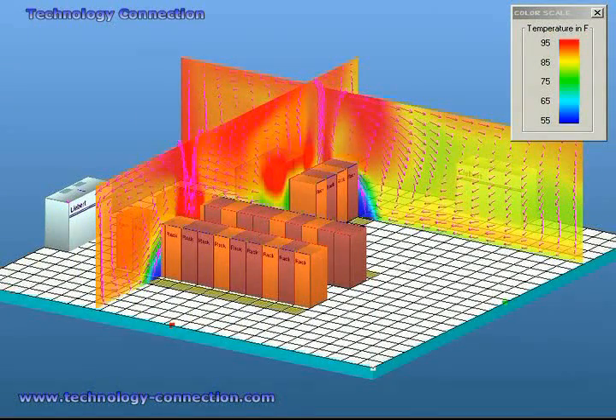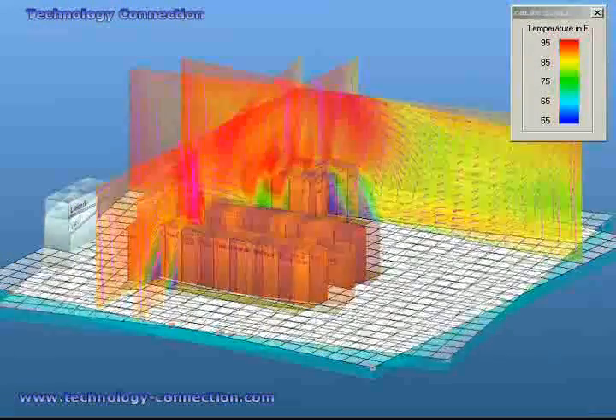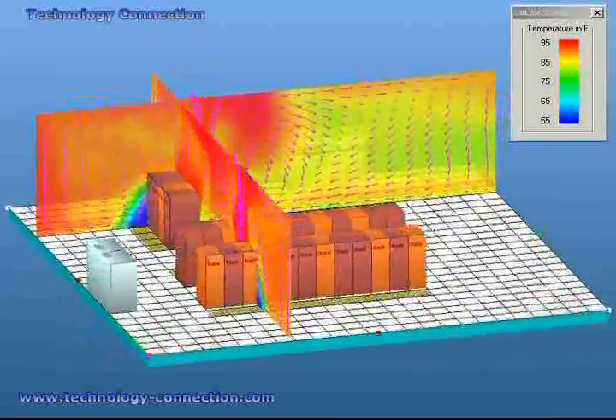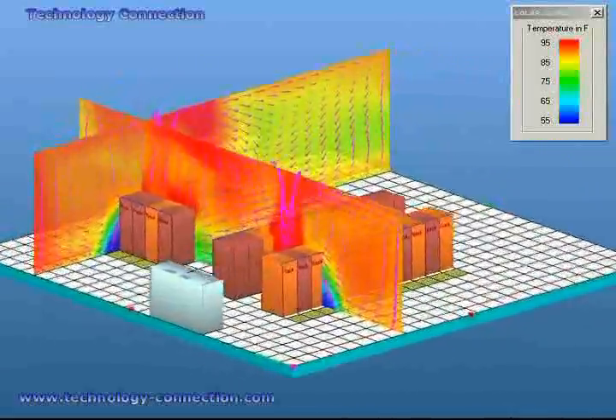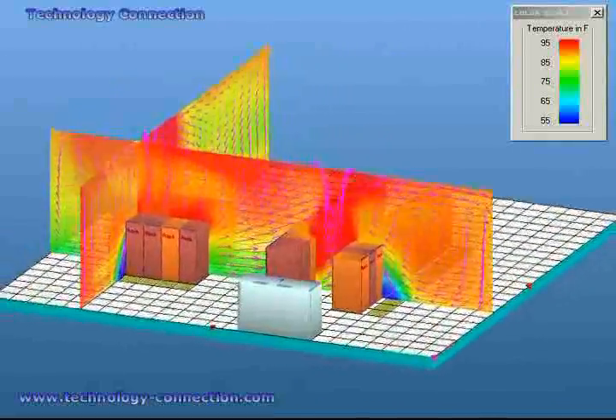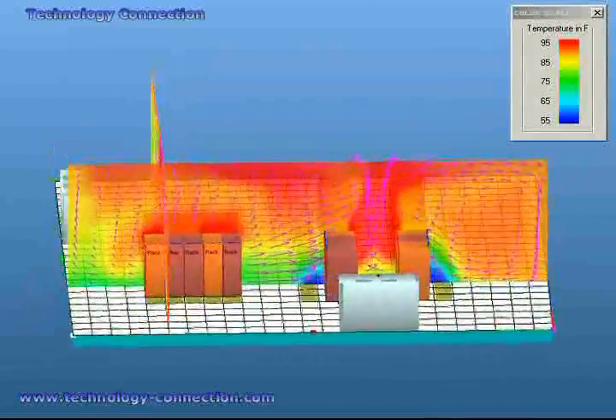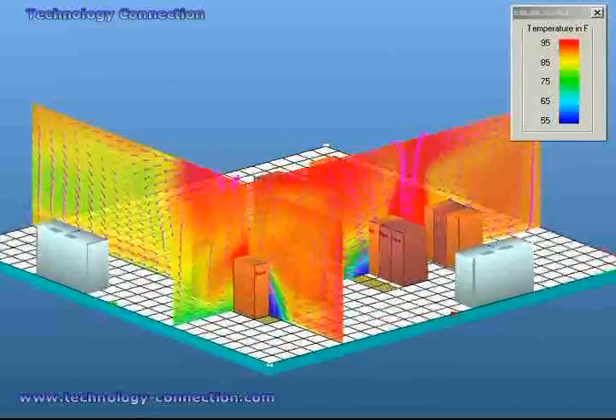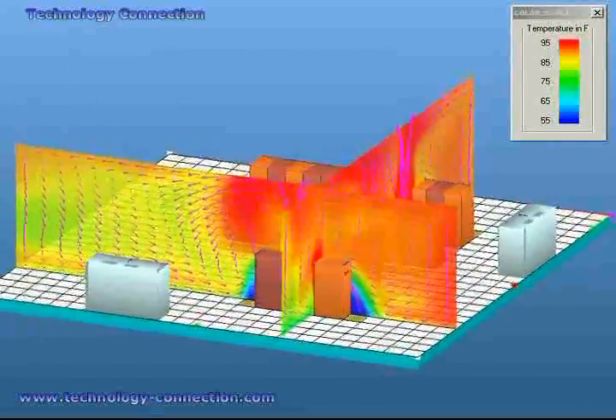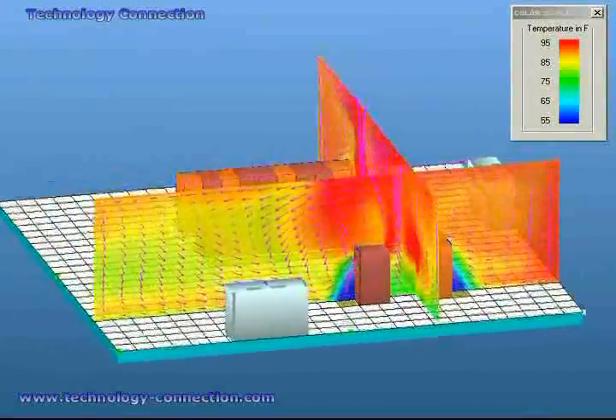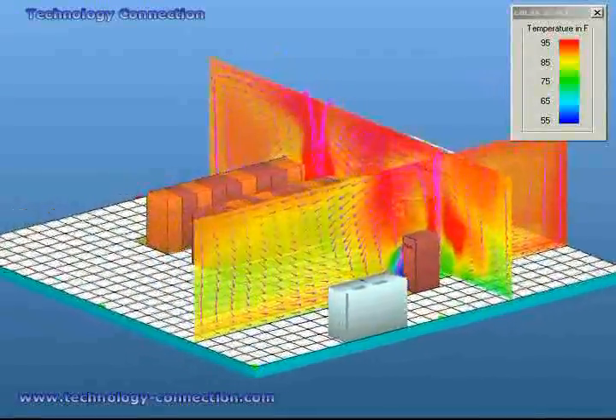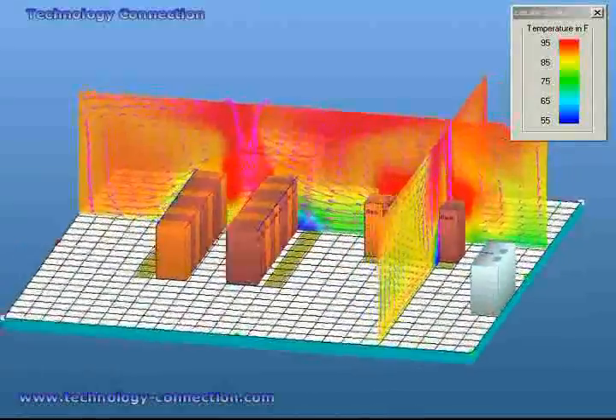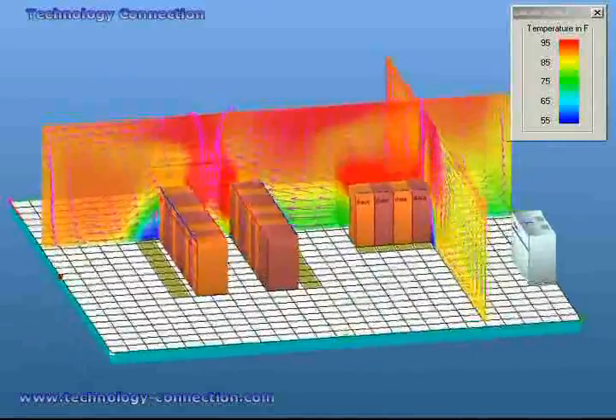Dual vertical planes can be viewed together, allowing us to truly pinpoint a coordinate within any ambient room and see how air reaches that point as well as how it disperses from that point. Customers use this as a cross section to determine how the air flows to a particular coordinate within their room. They are also used to visualize how air travels over top of equipment and allows customers to discover any airflow migration issues they may have within their room.